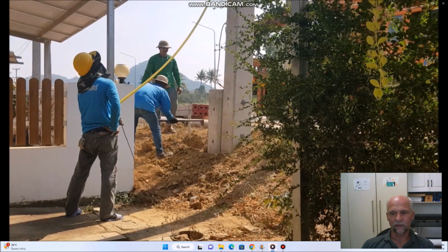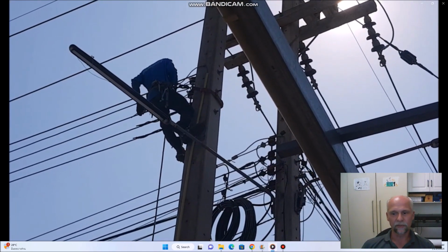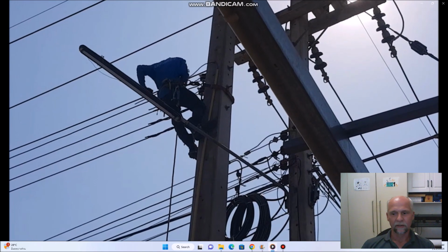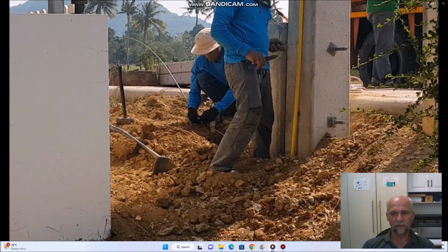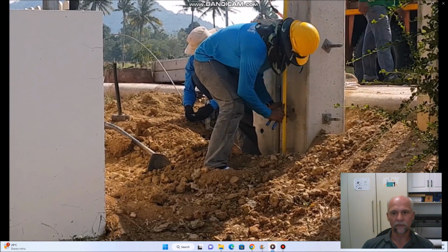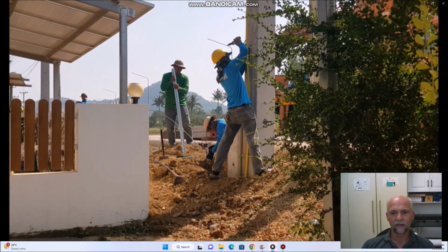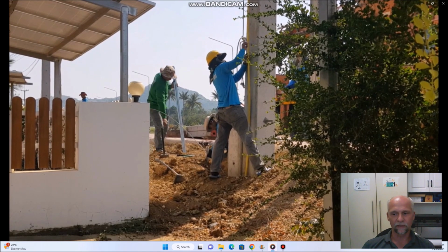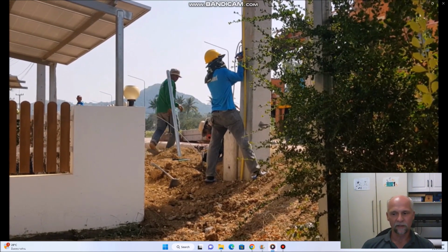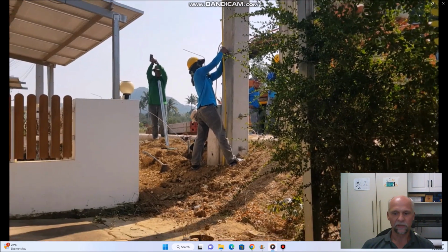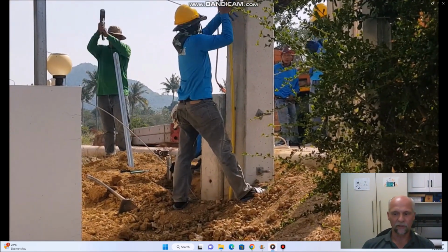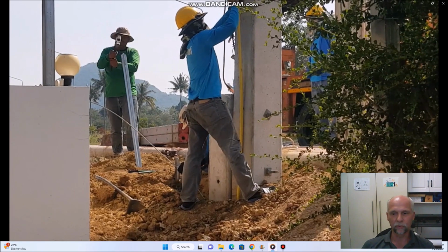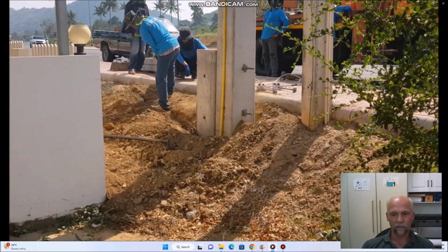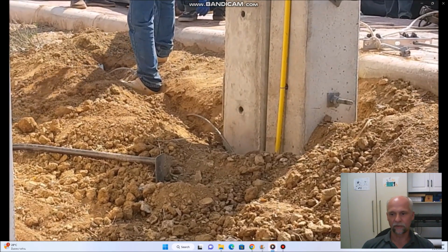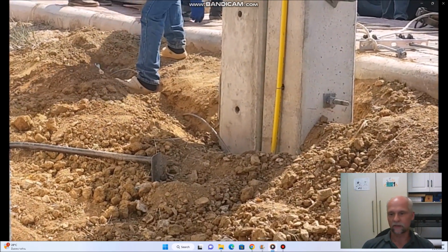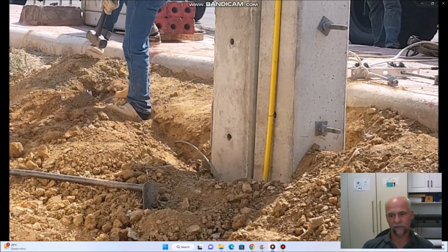Here we see the next day when they were working on the low voltage side of the distribution. Below the high voltage is the low voltage, which comes from the local transformer. This shows that the system here in Thailand is actually a TNC PME, or MEN, MGN, however it's called in your country—a multi-point earthing on the way to the consumer, where the neutral line is bonded again and again with ground.